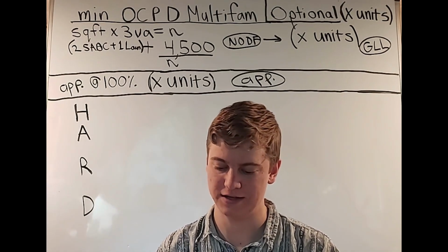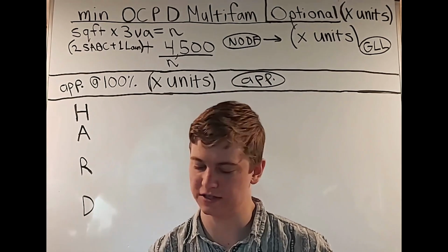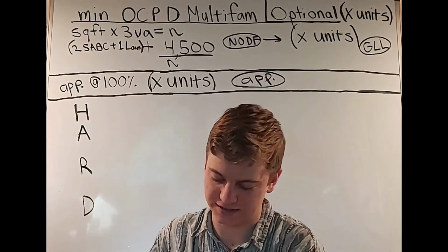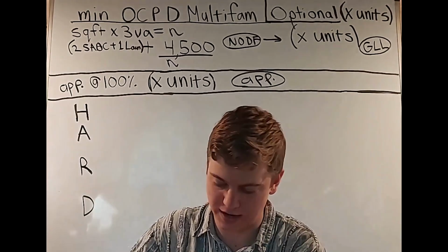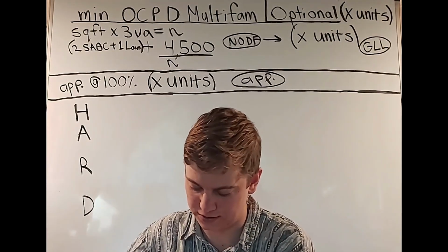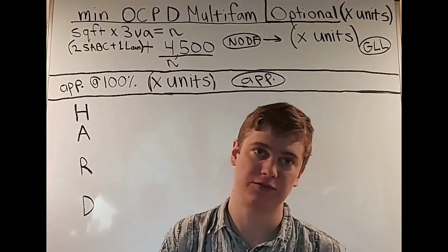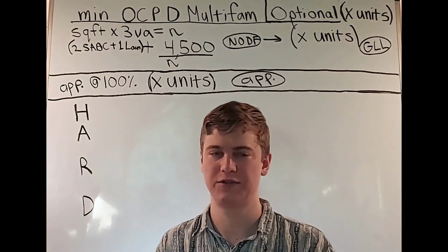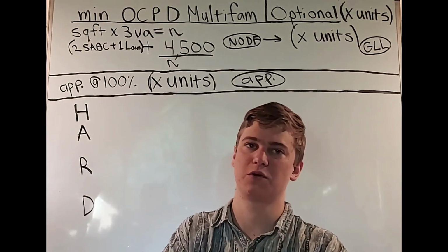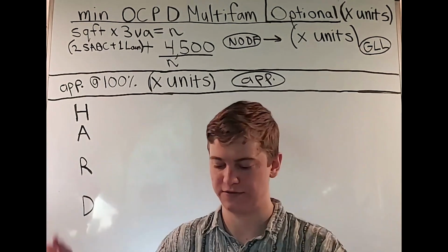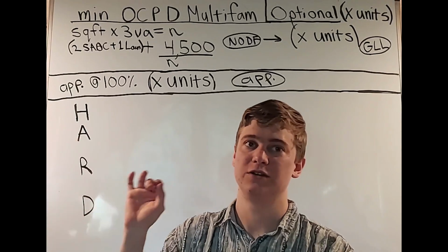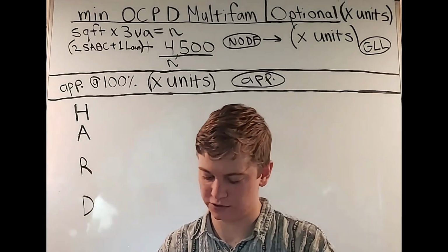This is not in the article. If you want to see this, if you go to article 220.82, you're going to see that section C is where you're going to find those demand factors for heating. You don't have demand factors for air conditioning, but you do for heating, but that's only for single family dwellings. Or if there's a question out of context, for example, if they don't tell you that you're working with a duplex or a multifamily, but if they say we have 6 space heaters using the optional method, what is the total demanded load?